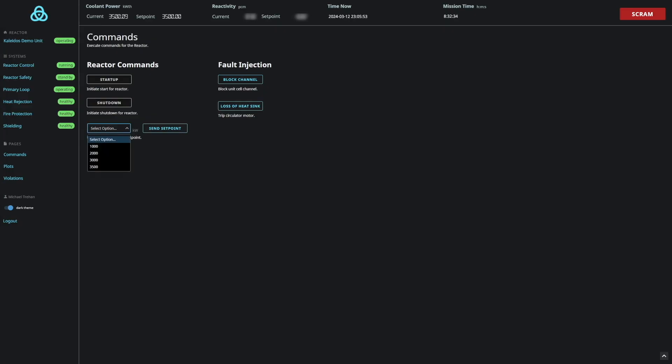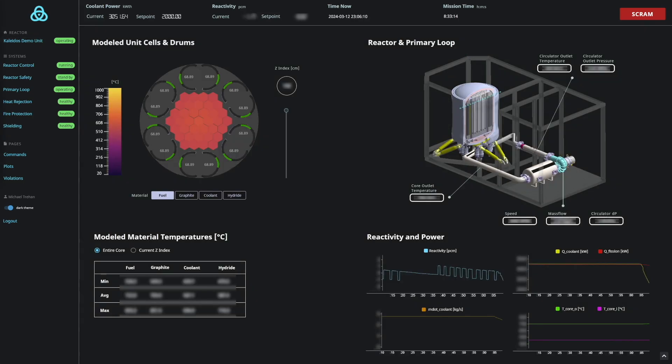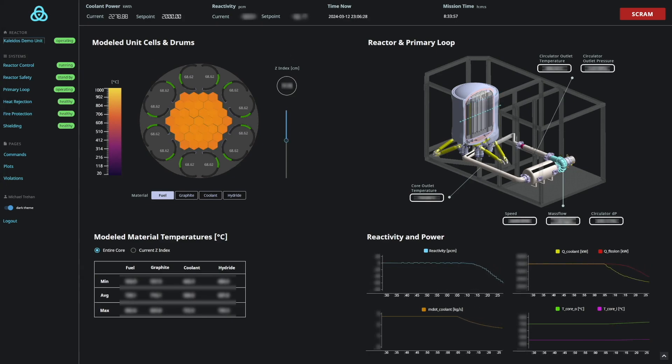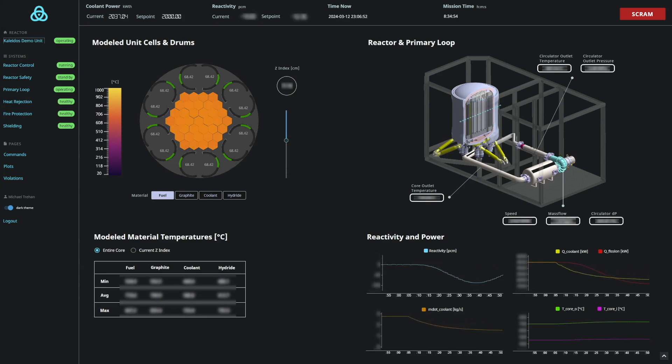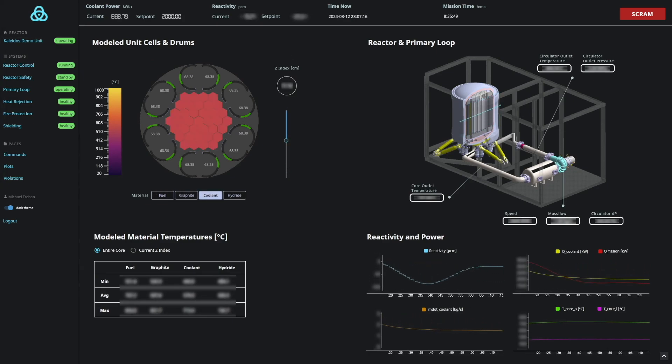Our next operation will be a reactor power setpoint change. In this scenario, we are changing the reactor's thermal power setpoint from 3500 kilowatts to 2000 kilowatts. The drums change their angle slightly, rotating inward to reduce reactivity.